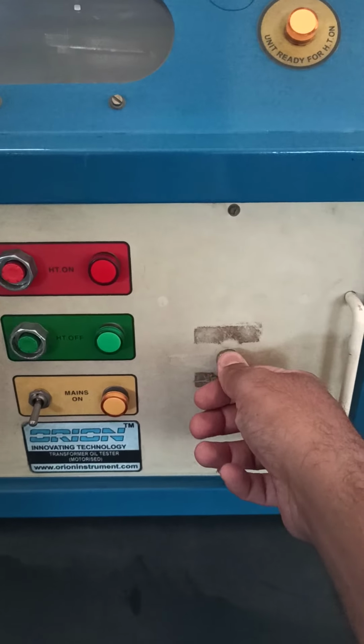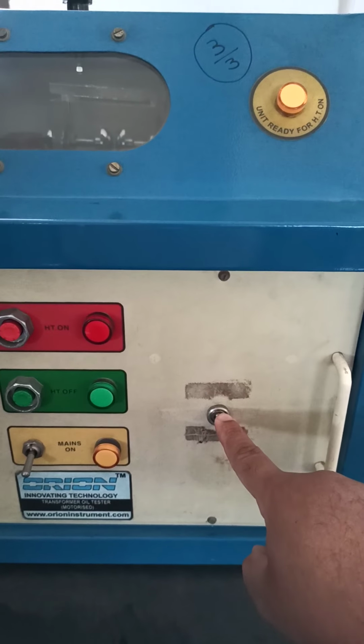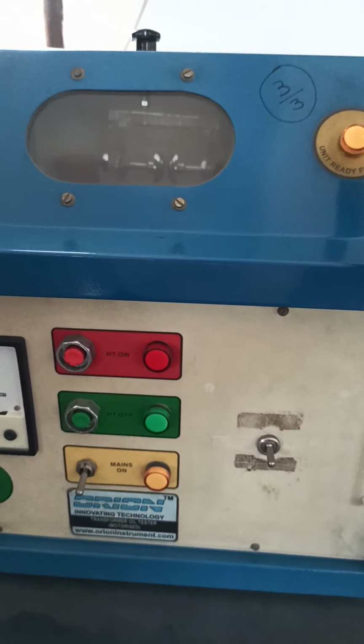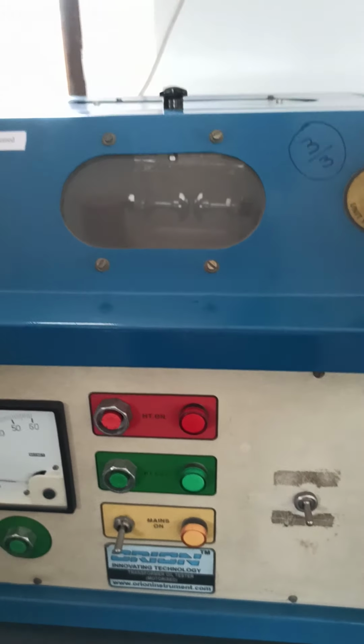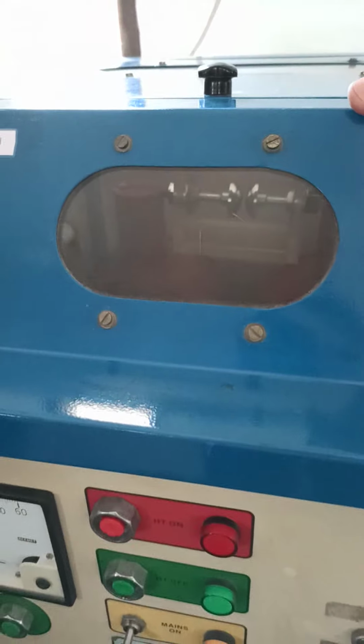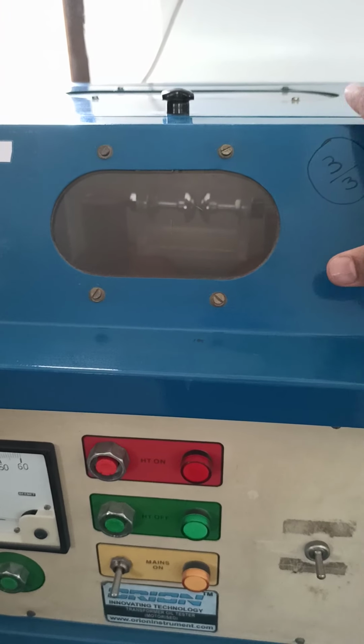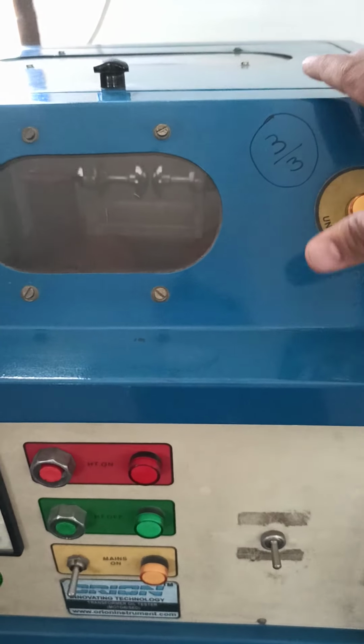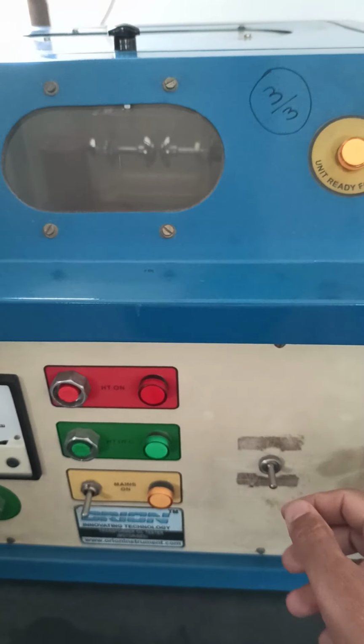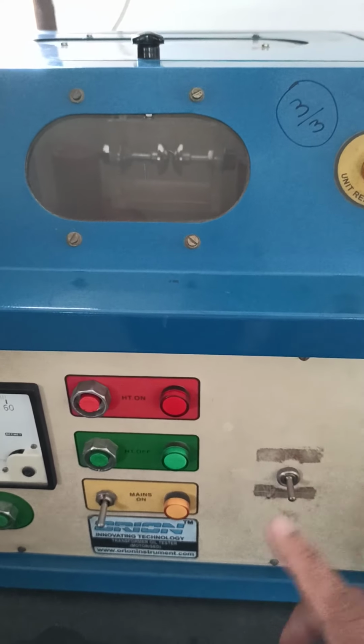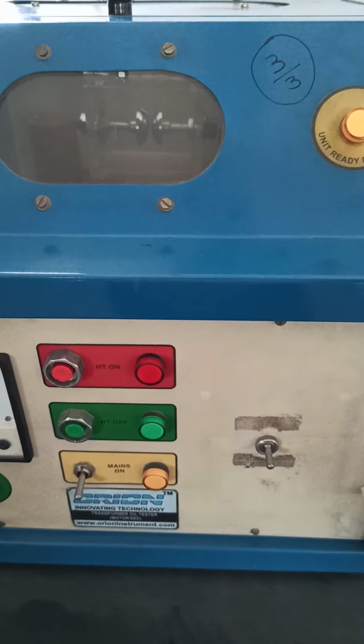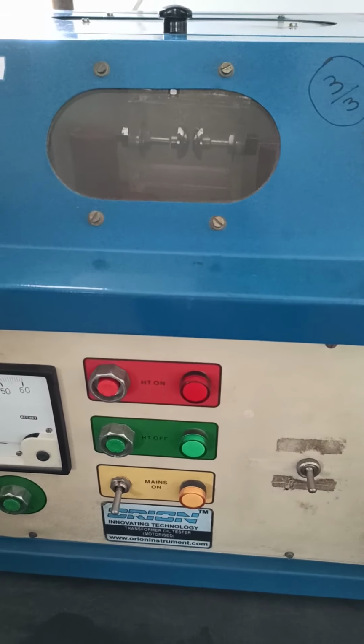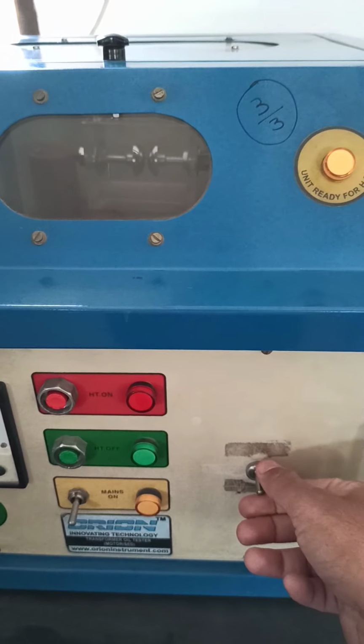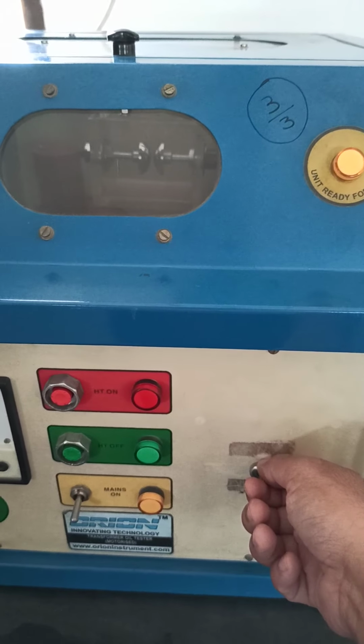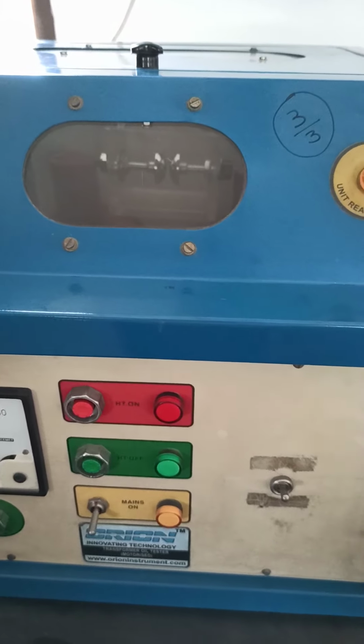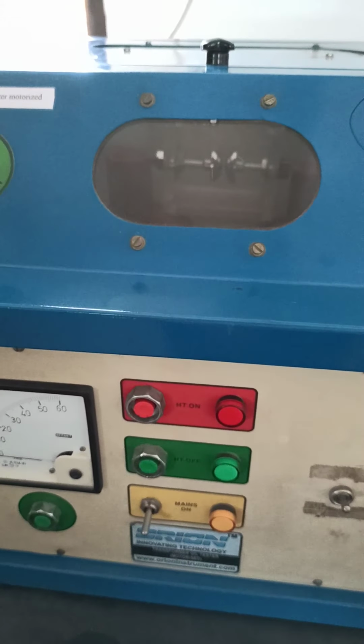So this is one switch which is given over here. This switch is actually given for the motor which is provided inside this, because in this we are having a step up transformer, a variable transformer. So to vary the windings of that transformer, we are having the motor inside this. That motor you can rotate in forward and reverse. Once you do the test, the motor rotates in forward, and again you have to reset the motor to the 0. So for that you will move this switch to the upper position so that the motor returns back to the 0 point, for the next test.